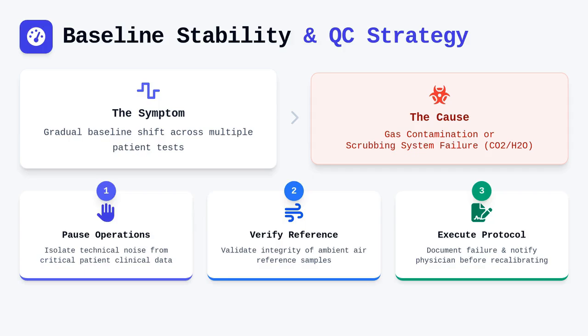It is a fundamental responsibility to ensure that the patient's clinical data is not conflated with technical noise. If the quality control status remains suspect, you must establish clear, predetermined protocols for stopping the diagnostic run, informing the attending physician, and documenting the failure before conducting any corrective maintenance or recalibration activities.